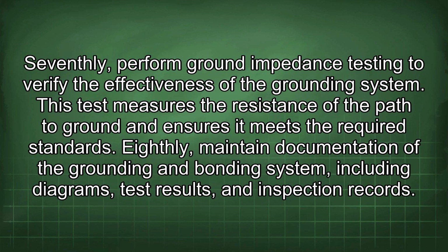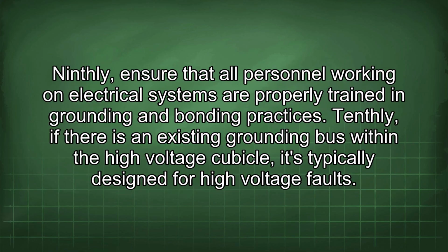Seventhly, perform ground impedance testing to verify the effectiveness of the grounding system. This test measures the resistance of the path to ground and ensures it meets the required standards. Eighthly, maintain documentation of the grounding and bonding system, including diagrams, test results, and inspection records. Ninthly, ensure that all personnel working on electrical systems are properly trained in grounding and bonding practices.